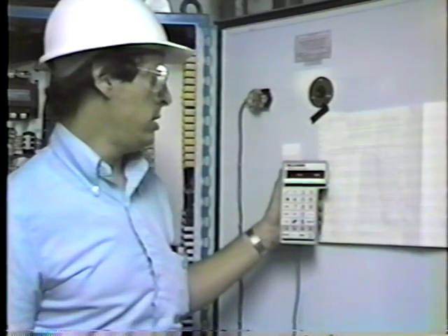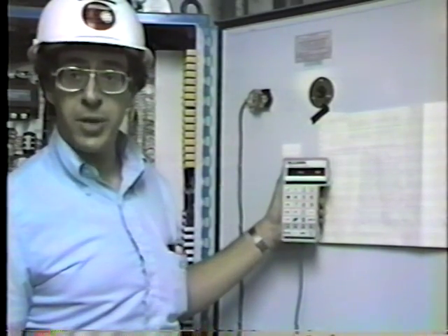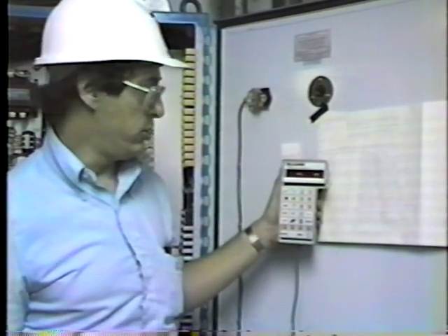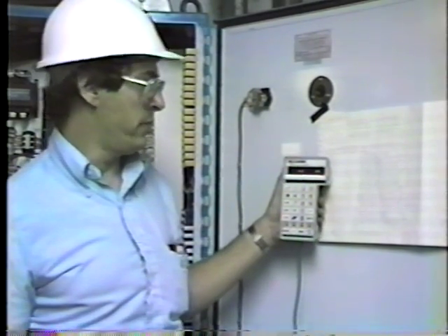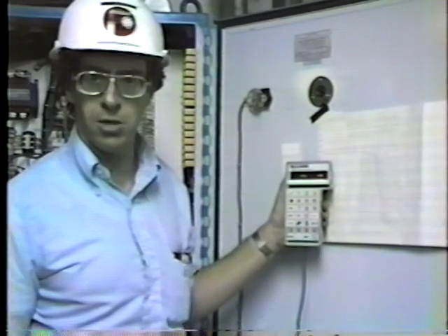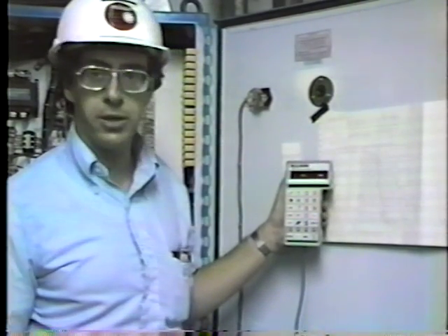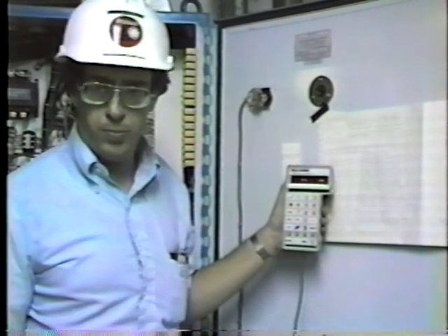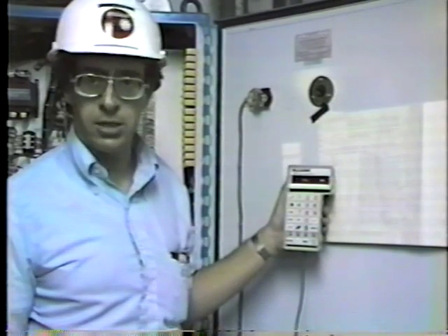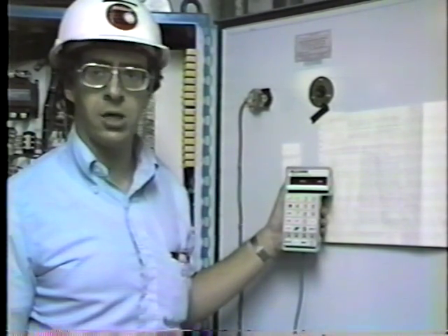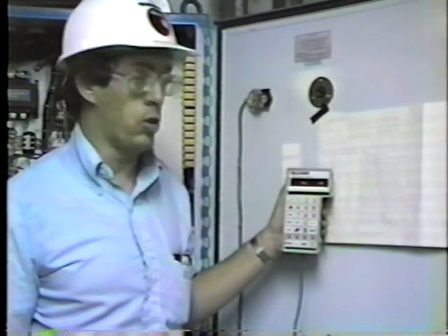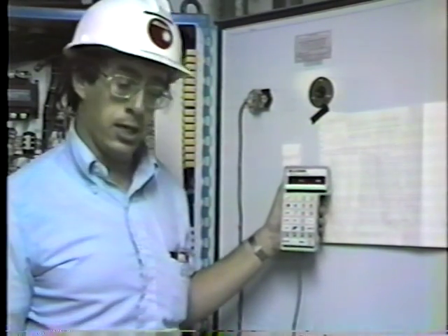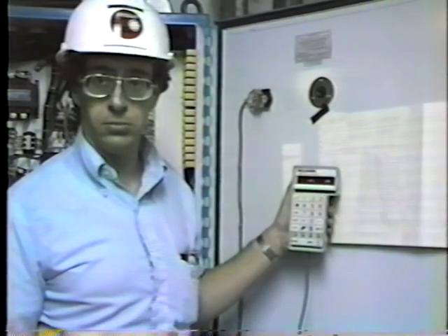Number 19, now at this point we're out of the pairs of values. Number 19 is the spinner speed minimum alarm value. We currently have it set to 0, and we'll probably come up with a setting of about 5%. This is the alarm value. The computer looks at the spinner tach, and if it ever sees the spinner tach go below this value, it shuts the mill down. All right.